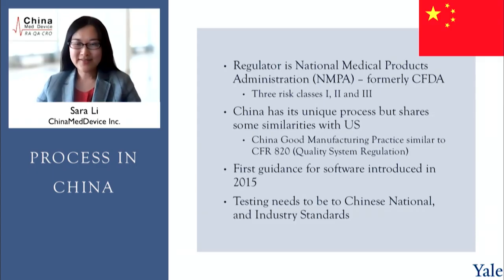In China, the National Medical Products Administration is the leading authority who evaluates a medical device conformity before being placed on the market. So China NMPA has a similar role as FDA in the review and approval of medical devices. The China GMP regulation is similar to FDA's requirements in CFR Part 820, and China NMPA may ask for a QMS audit to oversee medical device manufacturers.